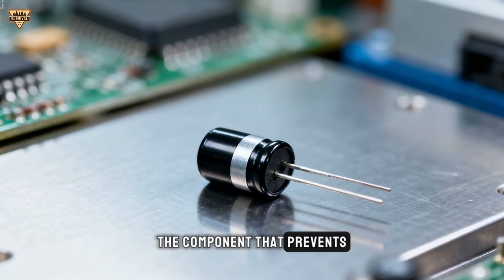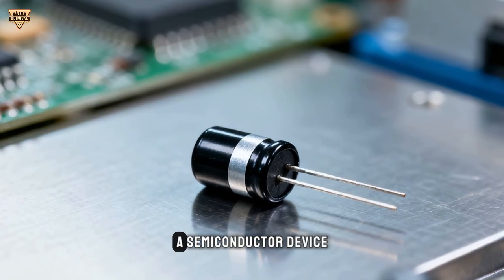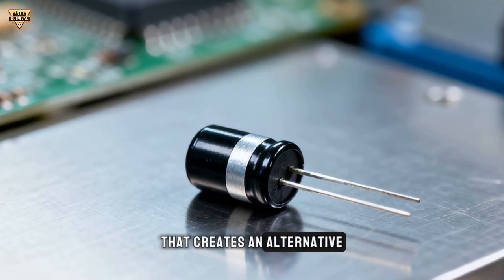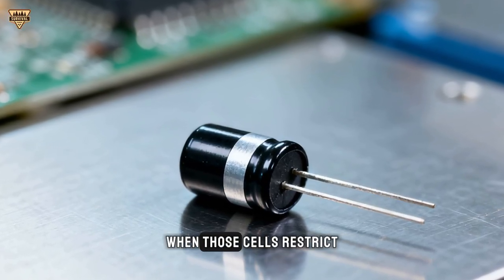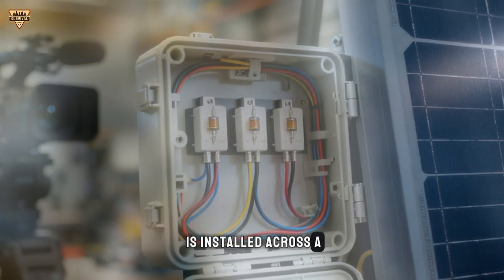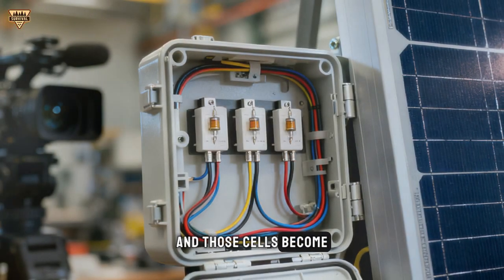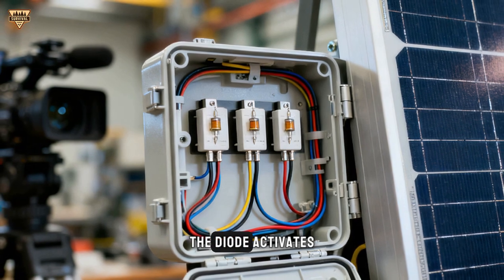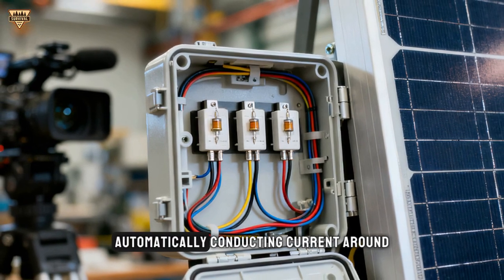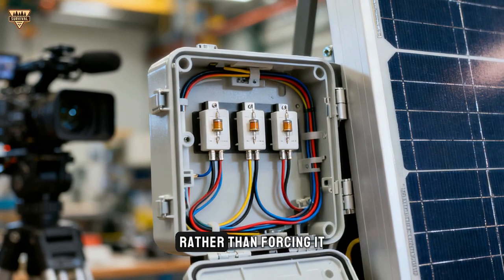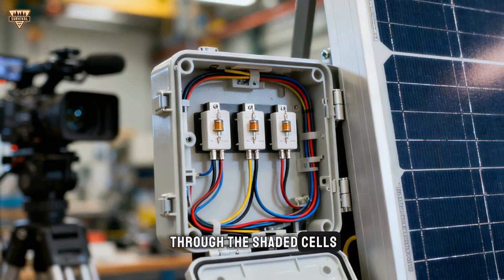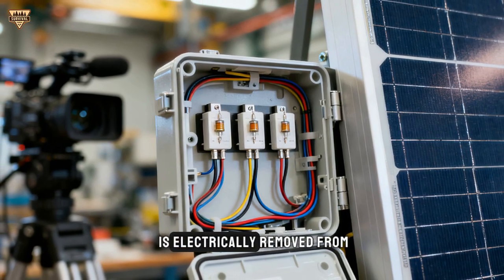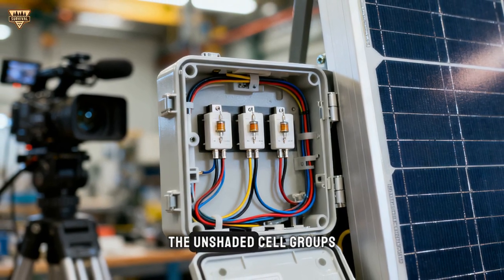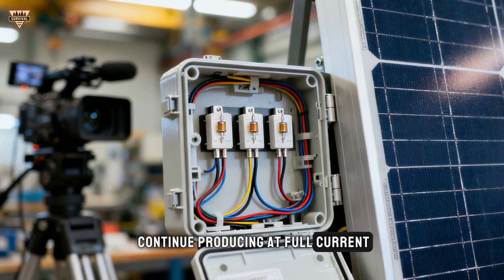The component that prevents this is a bypass diode, a semiconductor device that creates an alternative current path around shaded cell groups when those cells restrict current flow. When a bypass diode is installed across a group of cells, and those cells become shaded and current limiting, the diode activates automatically, conducting current around the shaded group rather than forcing it through the shaded cells. The shaded cell group is electrically removed from the series circuit. The unshaded cell groups continue producing at full current.